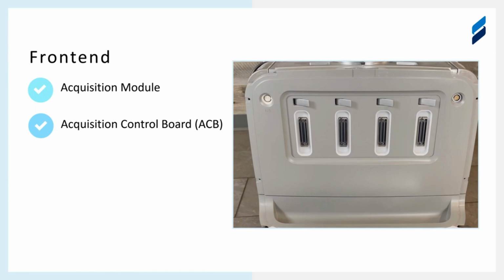The acquisition control board is technically a front end item, but it is inside the e-box, so just bear with me on the system architecture here. There's that gray area. It's physically inside the e-box, which is technically a back-end item, but its functions are really beamforming and controlling the acquisition module, which technically makes it a front-end board.